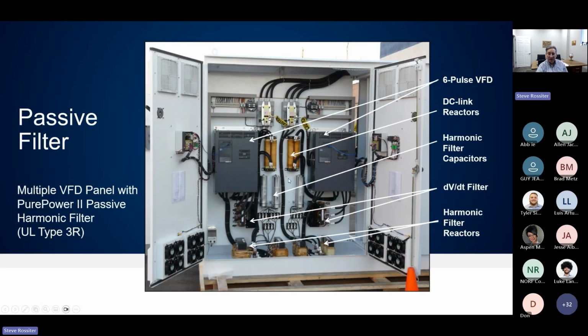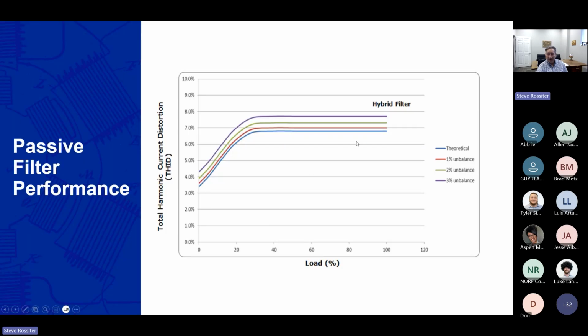In our drive systems, we integrate that harmonic filter along with DC inductors and other devices to create a drive system with harmonic mitigation, so that at the source, you can only be putting back onto the line the amount of harmonics that was designed for, which could be as low as 5% or, more economically, 15 or 20%. Those filters operate quite well, even with voltage variations. So with, let's say, a 5 to 8% range from 40% to 100% load, we had very good performance, even with voltage imbalance, which causes some technologies of harmonic mitigation to be challenged in maintaining the original input.